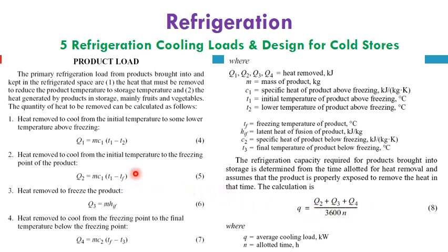However, if we just chill the product, not freeze it, keeping it above zero, such as fruits, dairy products or veggies, we can use only equation number 4. Also, we can consider the time to cool down this product if we use a freezing tunnel. However, it's rarely used for products that are only chilled, without freezing. We can use the product load, which will be loaded on the refrigerated equipment, without the need to add a freezing tunnel.